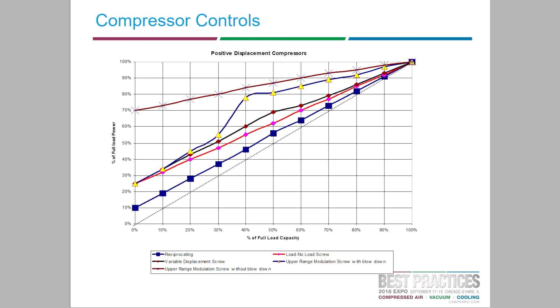One control that doesn't get talked about a lot, primarily because two of the largest producers of air compressors in the world don't necessarily offer it, is variable displacement, which a lot of people don't fully understand. I equate variable displacement to the adjustment of inlet guide vanes on a centrifugal compressor—it's very linear in how far it can turn down, and it controls pressure in a manner that's also energy efficient. They go by names like spiral valve, turn valve, poppet valve—different types of variable displacement products.